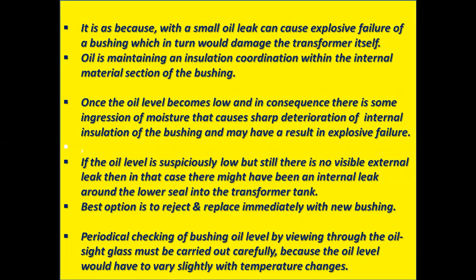If the oil level is suspiciously low but there is still no visible external leak, then there might be an internal leak around the lower seal into the transformer tank. The best option is to reject and replace immediately with new bushings. Periodical checking of the bushing oil level by viewing through the oil sight glass must be carried out carefully because the oil level varies slightly with temperature changes.